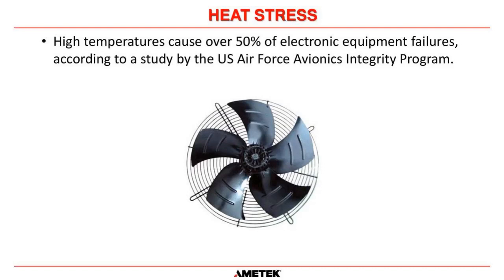Another mode of failure is heat stress. The US Air Force Avionics Integrity Program did a study, and they found 50% of electronic equipment failures were caused by high temperature. That's a huge amount of failures. And it actually goes back to the capacitors that we just discussed, because heat kills capacitors.